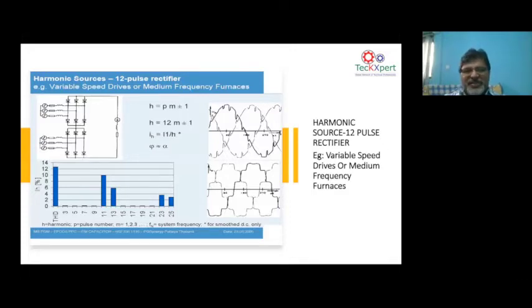As Mr. Murugesan said before, this can be a silent killer also, because these harmonics are not dominant when you connect an analyzer, but you should not neglect them. It is possible that these harmonics can be a killer tomorrow by means of an external transient coming into your plant and resonating at this frequency and increasing the voltage in the network. So you should be careful when you go into higher pulse drives to reduce the 5th and 7th. Go to the next.